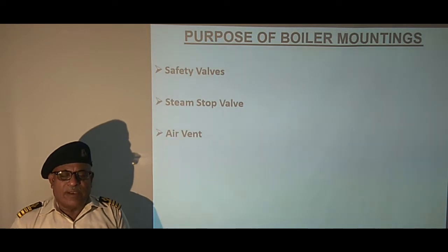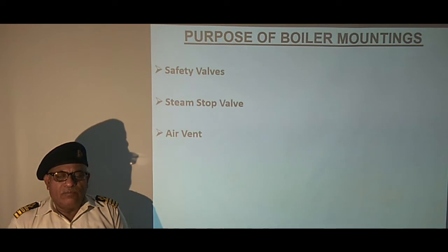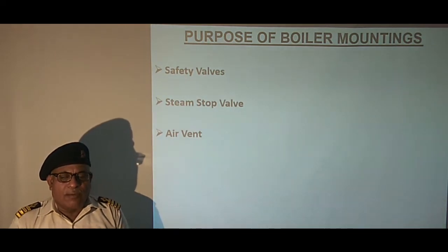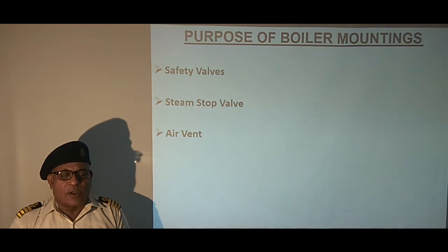Then we have air vent. Air vent is mounted at the highest point on the steam and water drum. Its purpose is to remove air from the boiler when filling up the water and raising steam. Air vent is opened while cooling down the boiler to prevent formation of vacuum inside the drum. Superheater is also equipped with an air vent whose purpose is to ensure a flow of steam through the superheater when raising steam after shutdown.